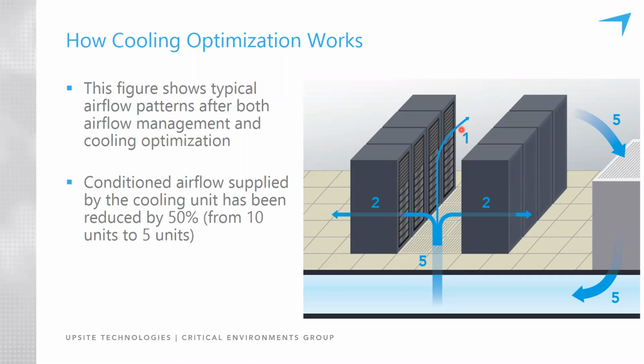So that's the concept of bypass airflow, and it's important to recognize the difference between the total amount of air moving through the room and the amount of air moving through the IT equipment. That's truly how you calculate bypass airflow: take the volumetric flow rate through the room and subtract the amount of air moving through the IT equipment, and what's left over is bypass, regardless of anything else in the room.